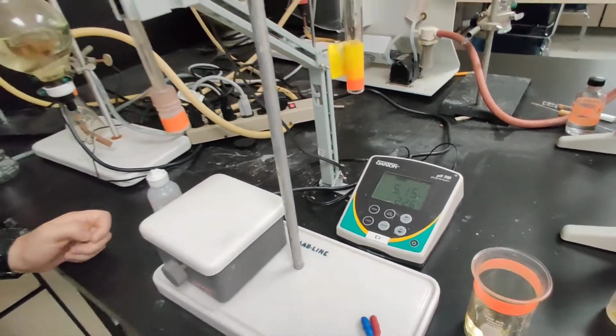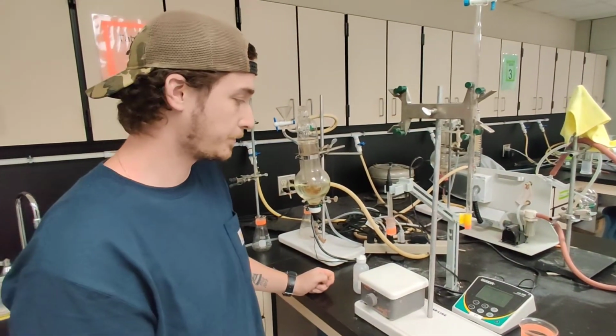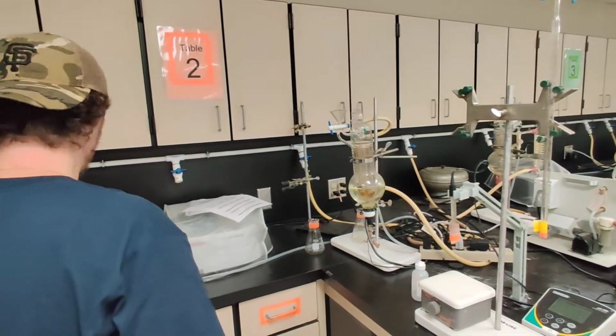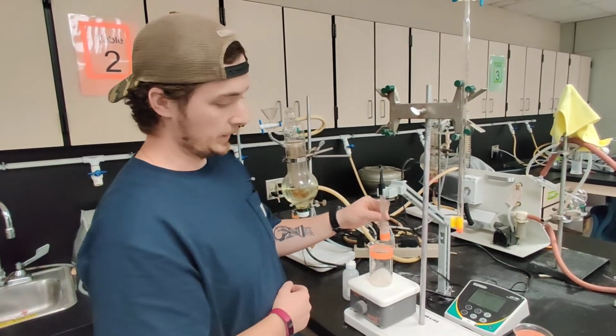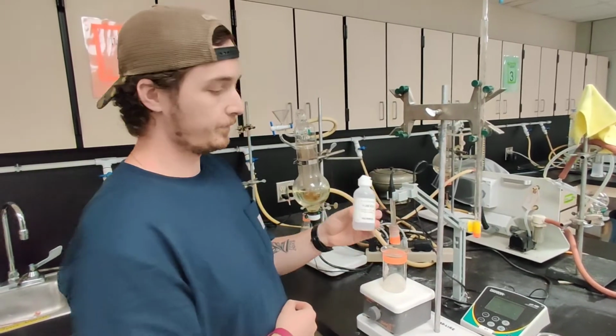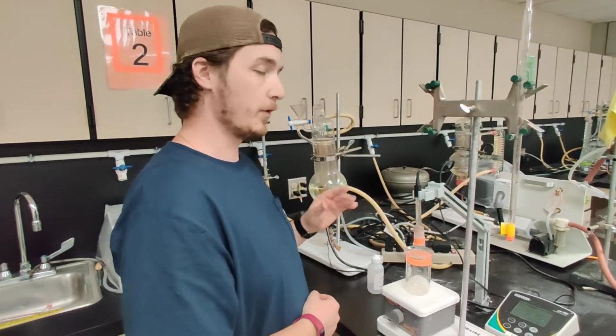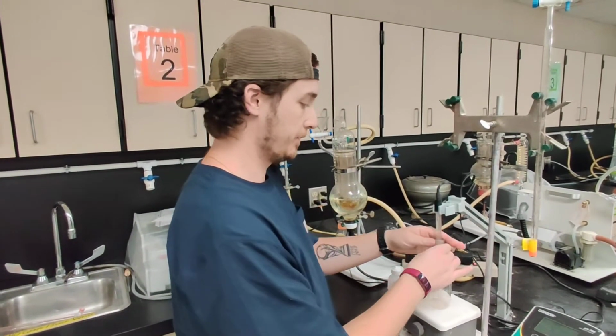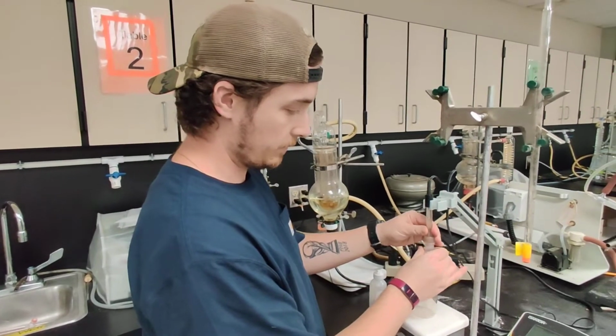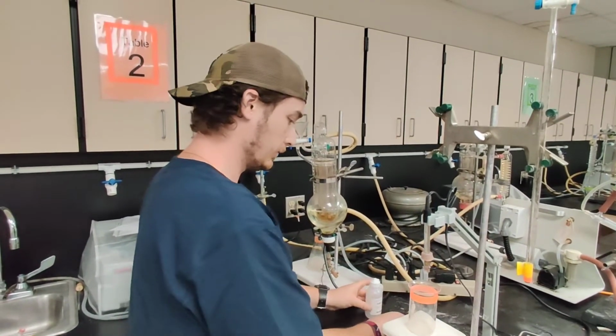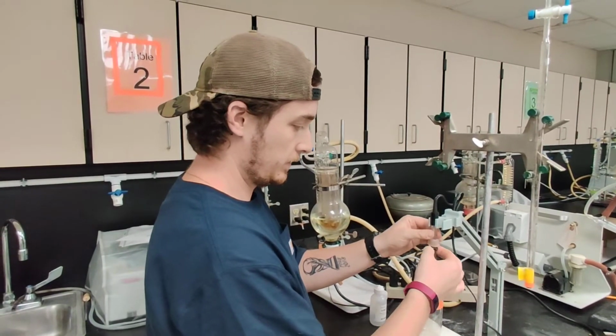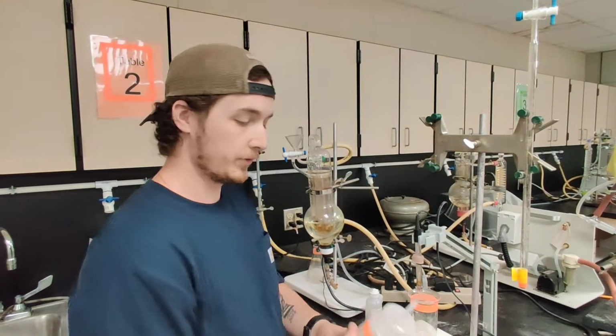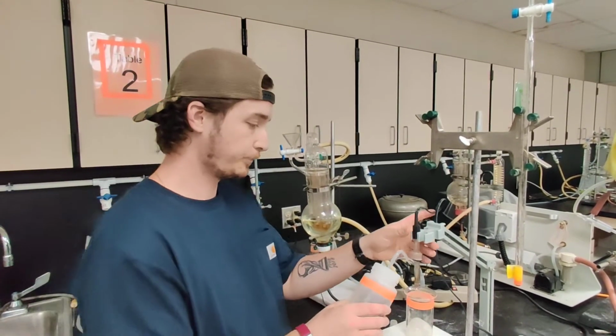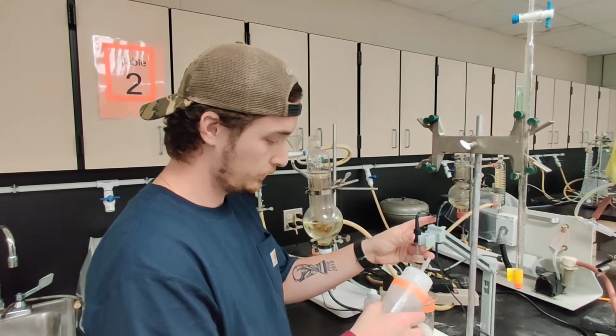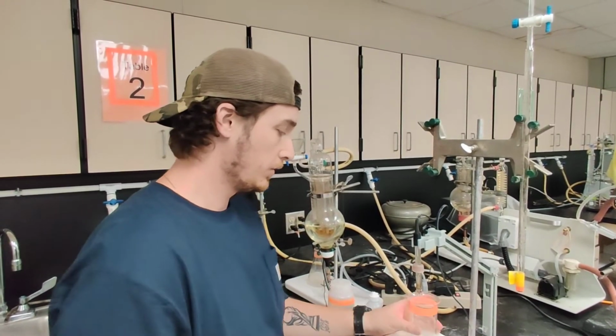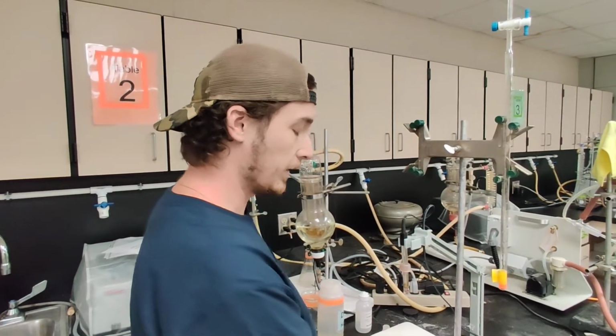Anytime you're about to use a pH meter, you want to calibrate it first. Note that the probe is stored in a storage solution that you find in these little bottles. You never want the probe to go dry, essentially. So we'll take the storage bottle out. What we'll do first is rinse the probe with DI water. And then we'll calibrate the pH meter.